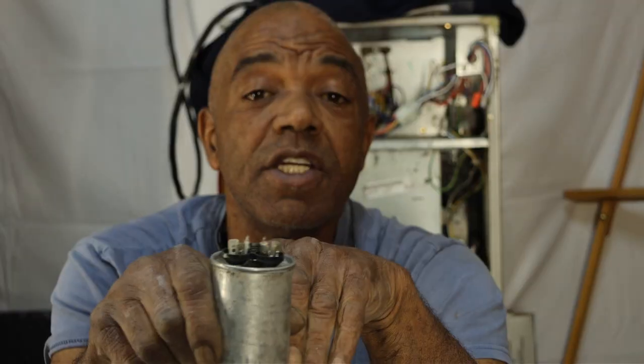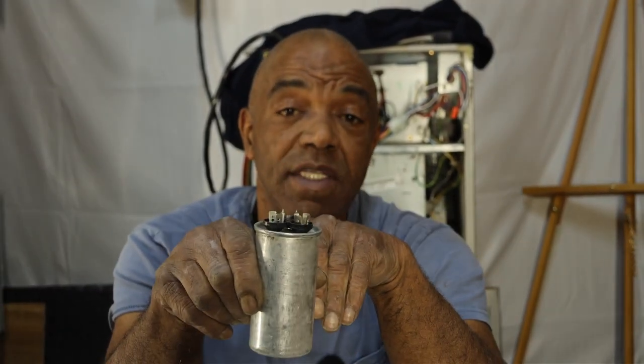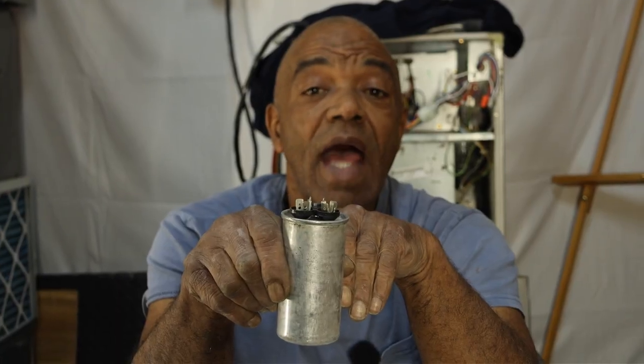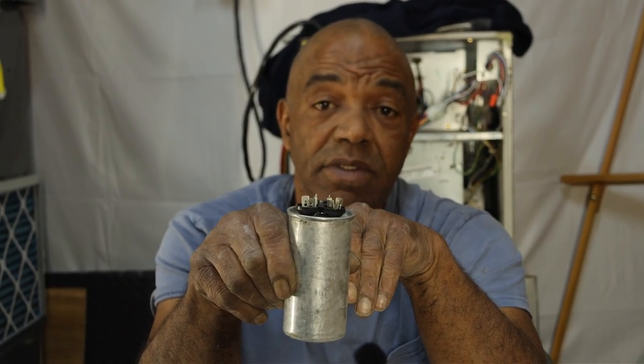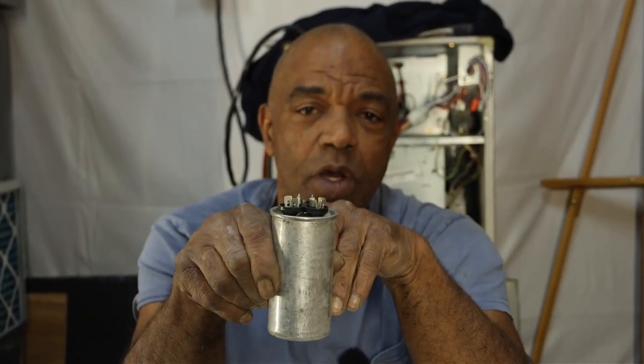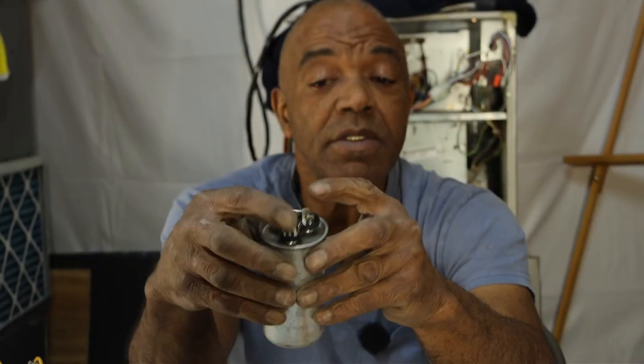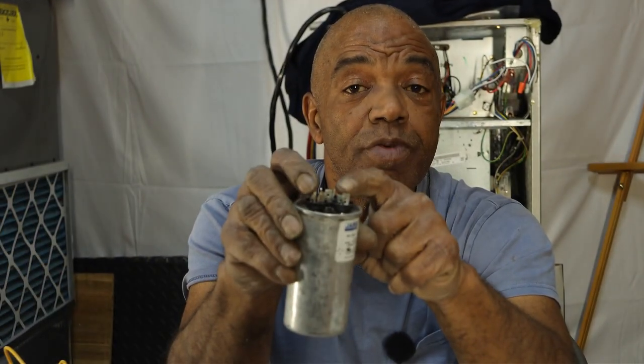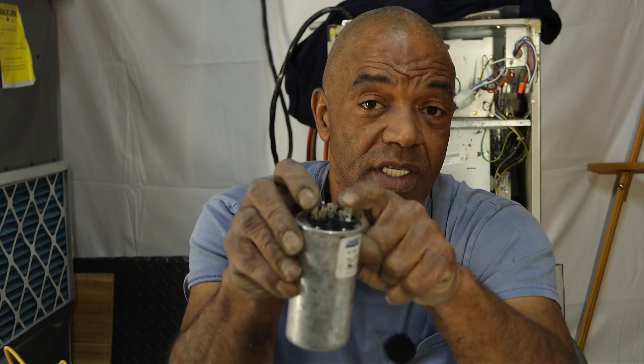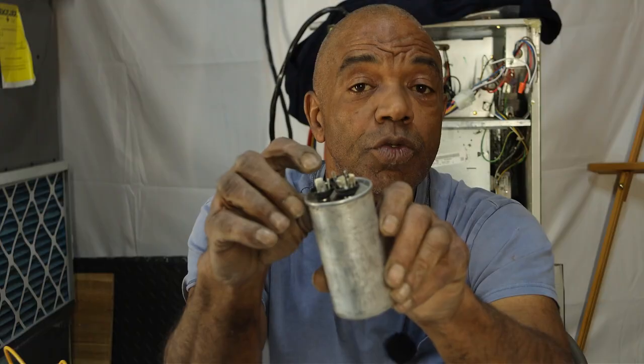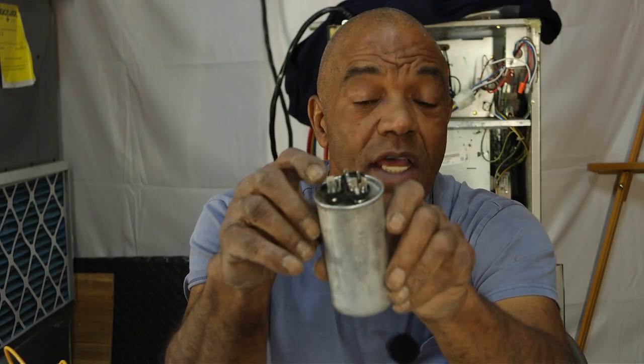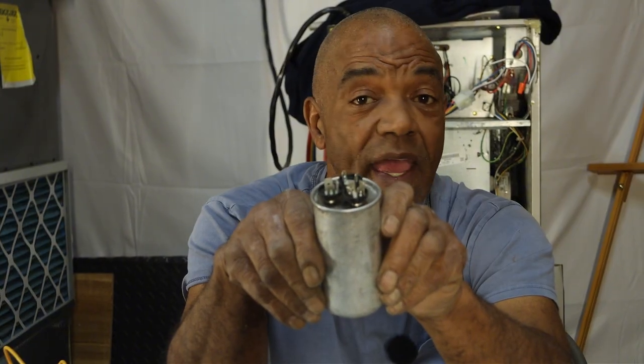Sometimes you'll come up to an air conditioning unit. You got a call for no AC, and when you arrive, the outdoor fan motor is running, but the compressor didn't come on. A lot of times, the problem is simply the capacitor. While the common to fan is still producing its proper voltage, the common to hermetic is not. Sometimes neither will work, the fan nor the compressor, and the whole problem is the capacitor.